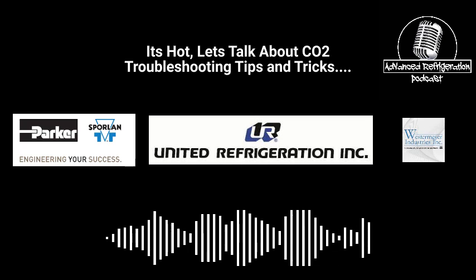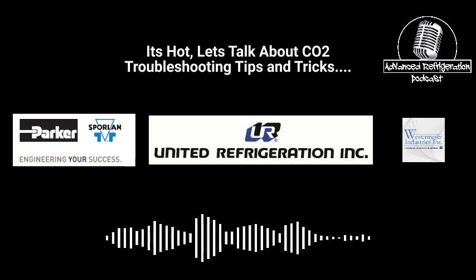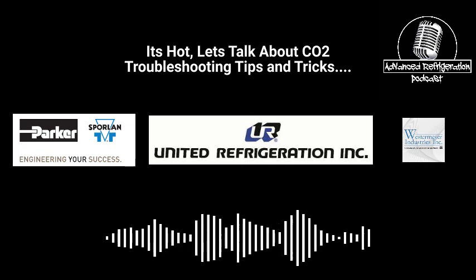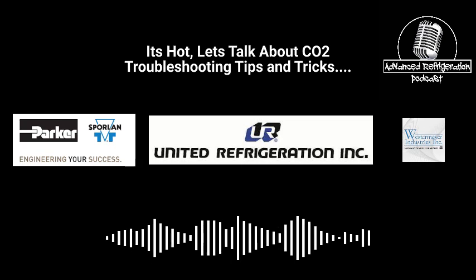And if it sees a liquid, it's going to send a signal back and close a set of contacts, depending on how it is. Some of these switches are normally open, some of them are normally closed. It's going to close or open a set of contacts to a valve or the EMS system to signal to drain oil. Now, generally, these are 24 volt DC, so just pay attention to them and make sure your voltage is correct.